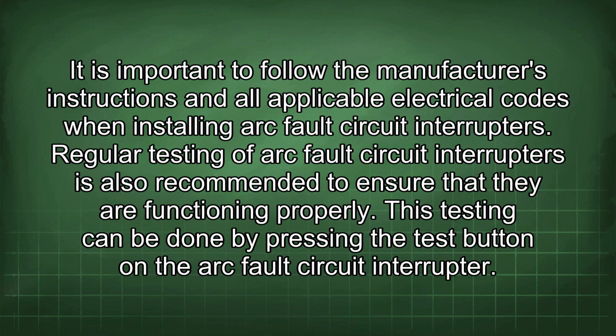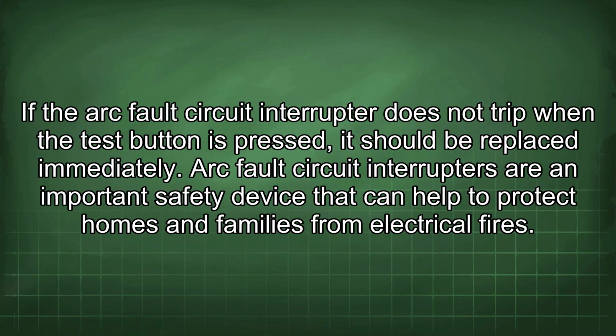It is important to follow the manufacturer's instructions and all applicable electrical codes when installing arc fault circuit interrupters. Regular testing of arc fault circuit interrupters is also recommended to ensure that they are functioning properly. This testing can be done by pressing a test button on the arc fault circuit interrupter. If the arc fault circuit interrupter does not trip when the test button is pressed, it should be replaced immediately. Arc fault circuit interrupters are an important safety device that can help to protect homes and families from electrical fires.